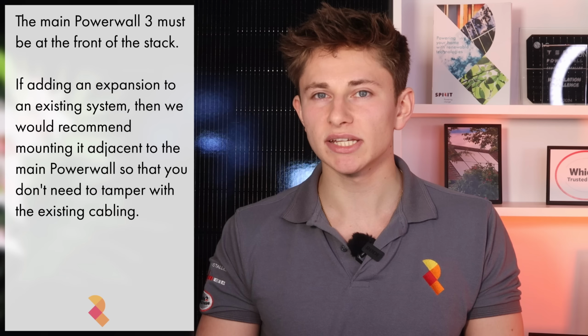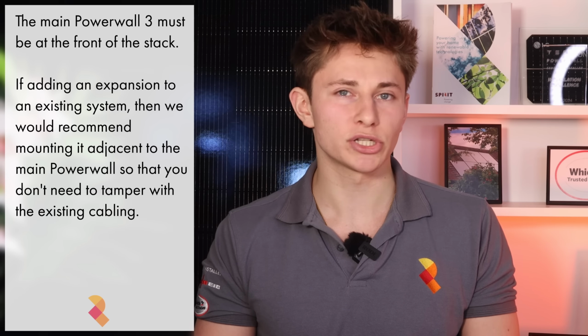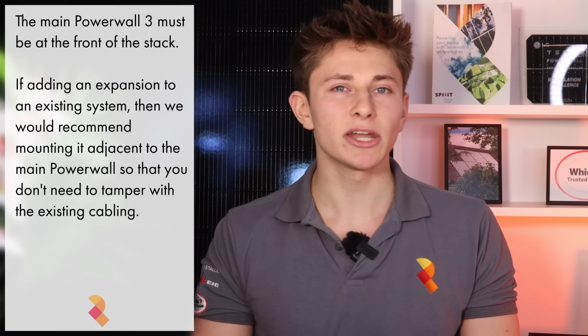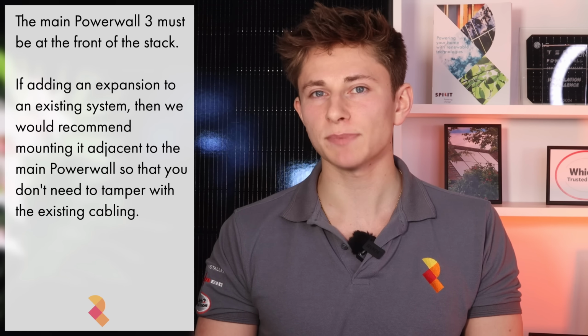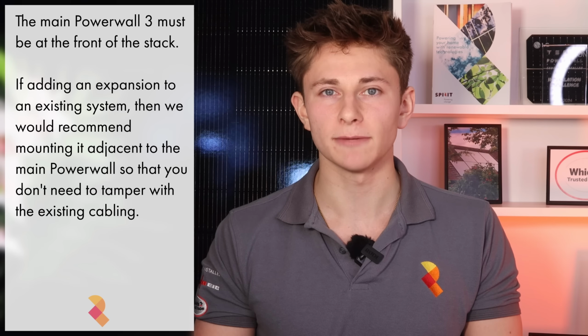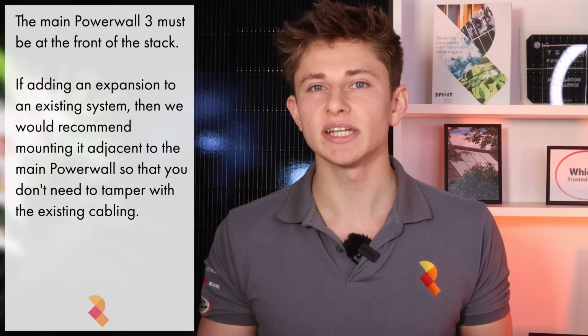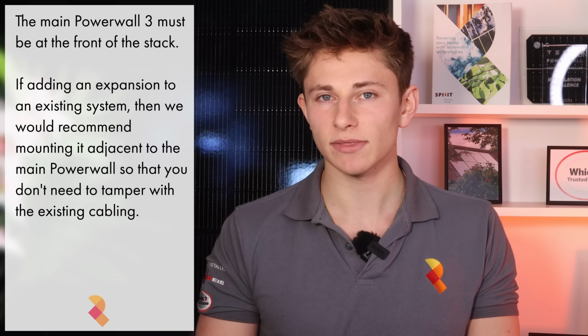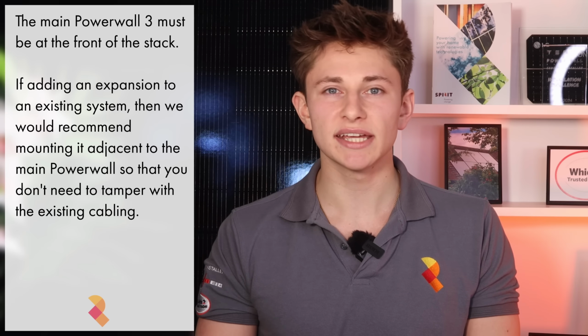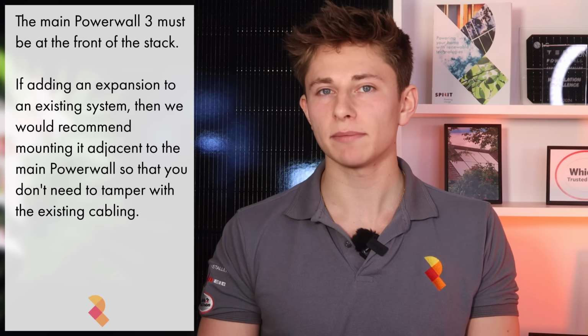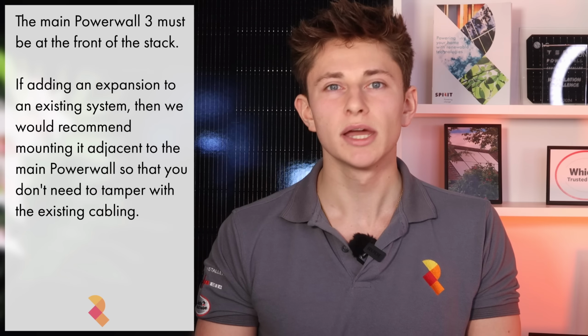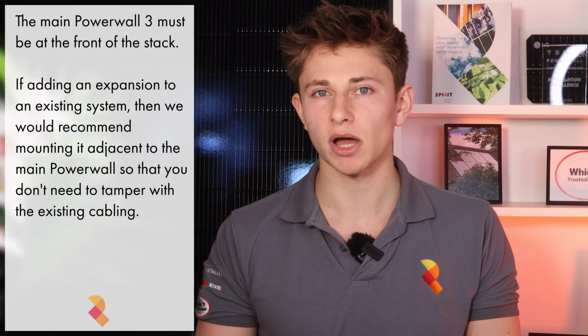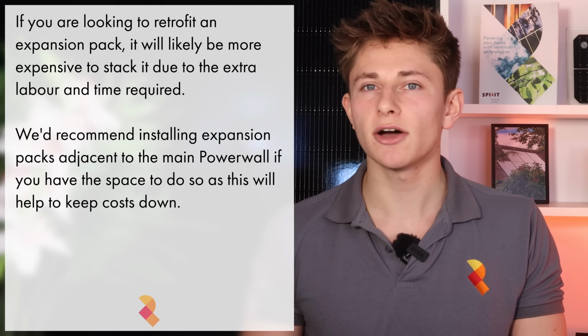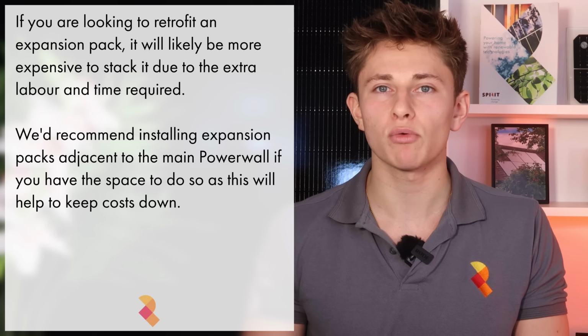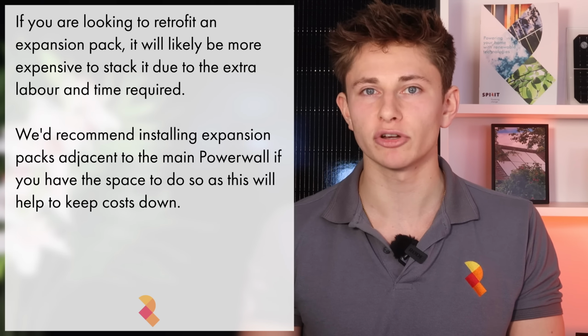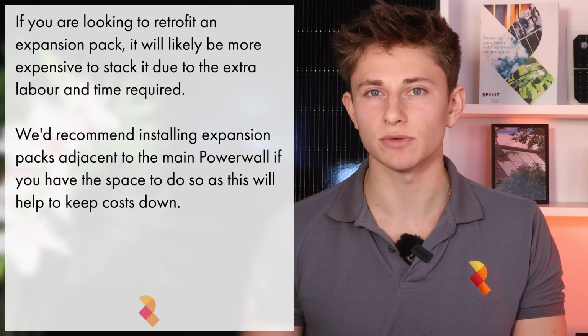That means that if you have an existing Powerwall 3 installed and want to retrofit an expansion pack, then I'd probably recommend installing the DC expansion adjacent to the main Powerwall 3. If you choose to stack the batteries, then your installer will likely need to disconnect the existing wiring and potentially extend the cabling in order to move the main Powerwall 17 centimeters forward to allow for the expansion pack to be fitted behind. All of this takes time, and it will cost more to stack a Powerwall 3 expansion pack if you're looking to retrofit one to an existing Powerwall system.